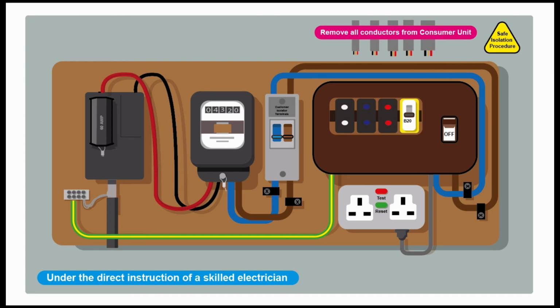To run a temporary supply, we put a B20 plug-in MCB in there, run a radial circuit to an RCD socket so we can get some power for the kettle and the battery chargers and a bit of light if we need it. We've removed all the conductors from the consumer unit, obviously under safe isolation. We've tested everything was dead. We've worked safely. We've removed all the conductors from the consumer unit, so we're happy that there's no energized circuits throughout the flat, throughout the house.